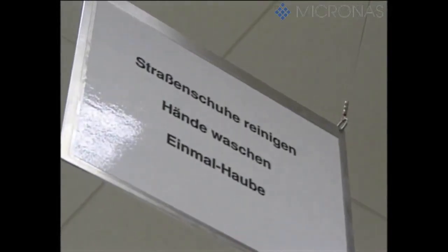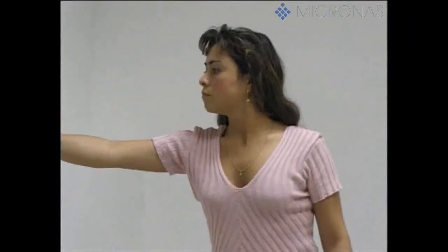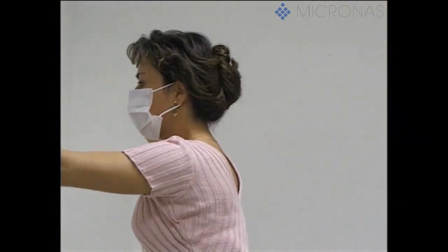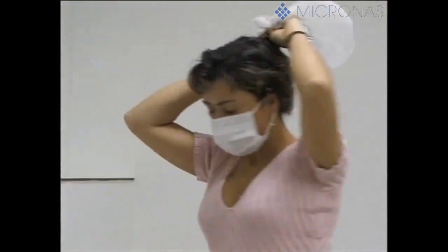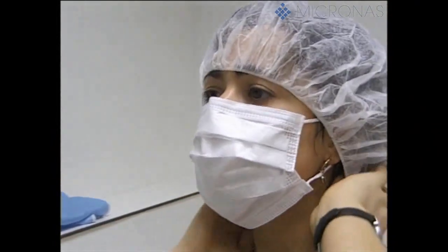To keep the clean room dust-free, all employees have to change their clothes in an elaborate procedure, because a clean room is required to be extremely clean. No more than one particle of dust with a diameter of 3/10,000ths of a millimeter is permitted in 1 cubic foot of air.